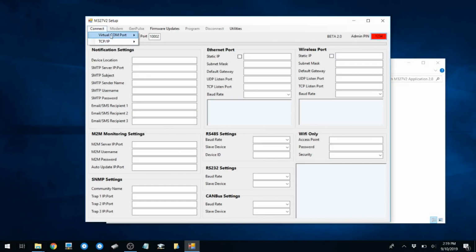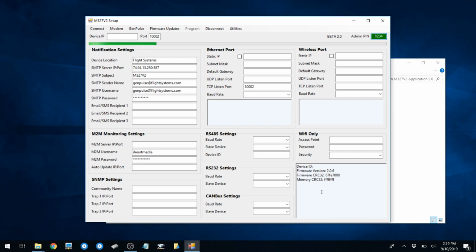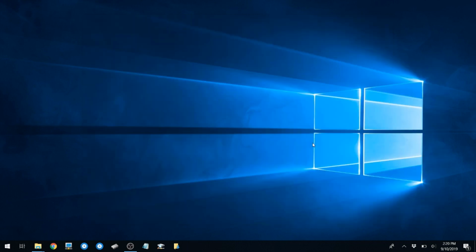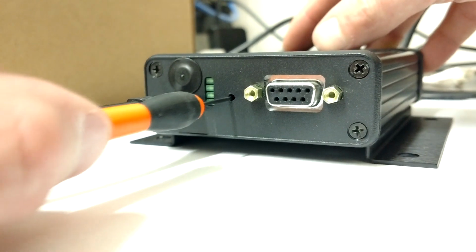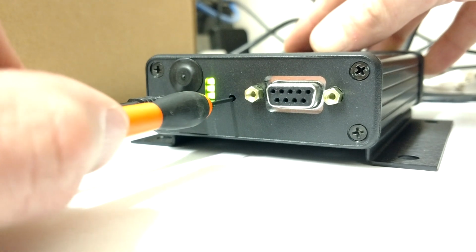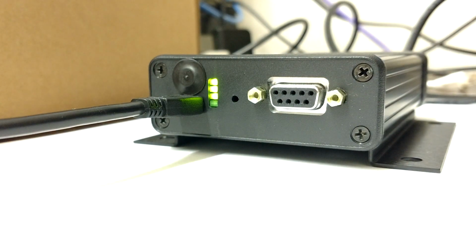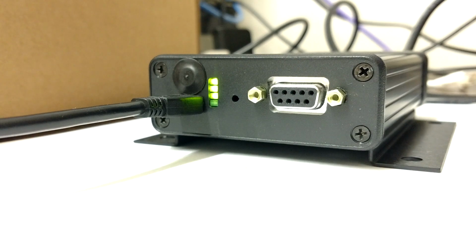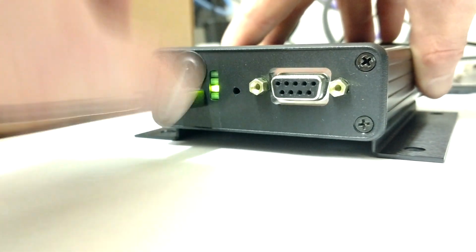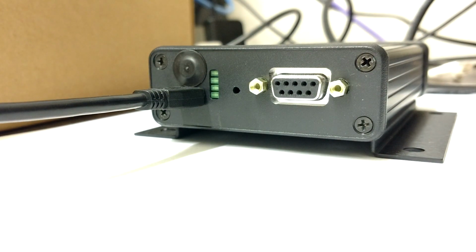If when connecting to the device, you do not see a device ID listed, you may have applied factory defaults before the Grid Connect module was ready to respond. If that is the case, let the device sit idle for a minute and then perform a factory reset again. Using a small tool, push and hold the reset button. Hold it until the lights start flashing, then release and push again. Once you see the lights start flashing rapidly again, remove power from the device and then plug the power back in. The device is now at factory defaults.